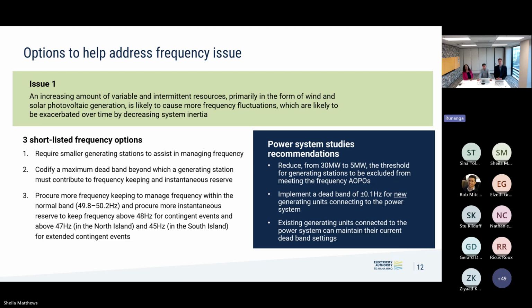The second option is to formally introduce a deadband into the code. At the moment the code is silent on whether a deadband is required. What we're looking at is putting in place a deadband beyond which a generating station must contribute to supporting frequency, including frequency keeping and instantaneous reserve.